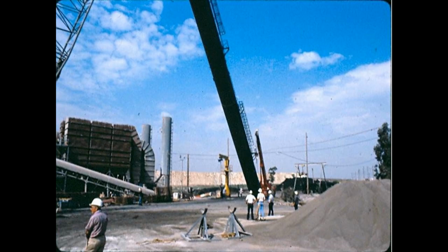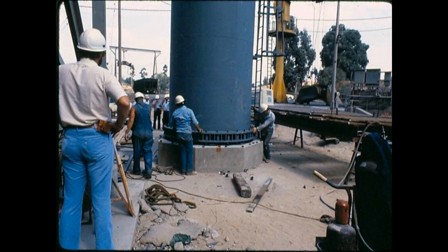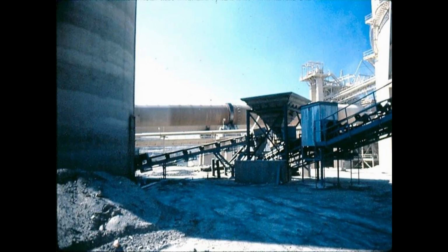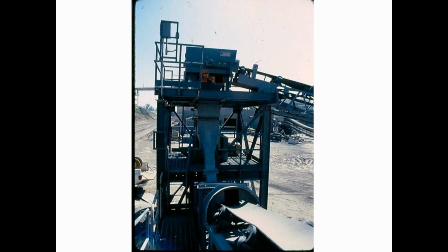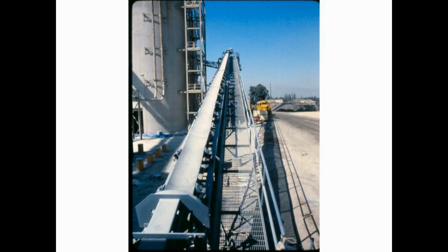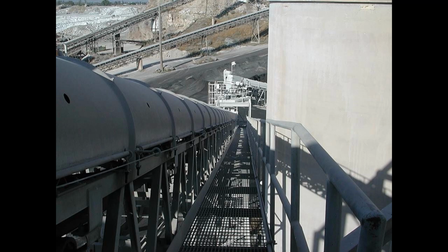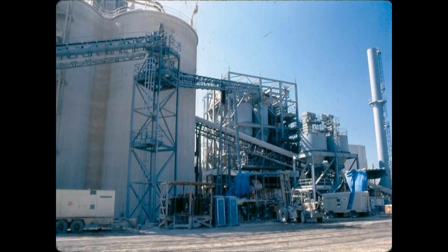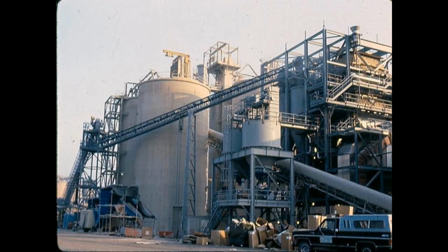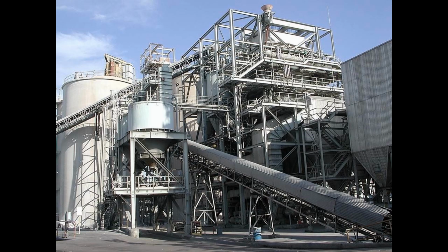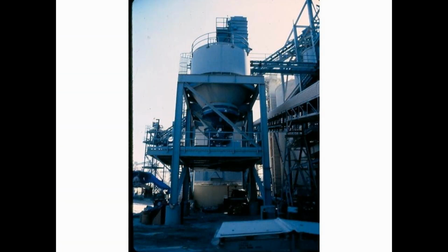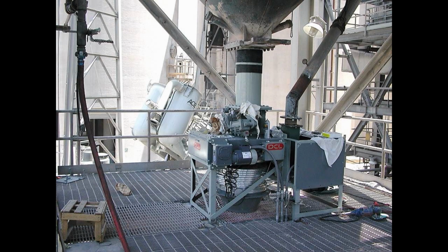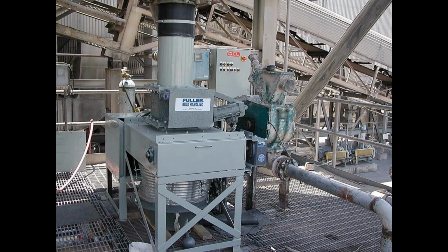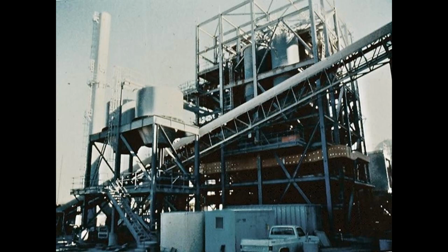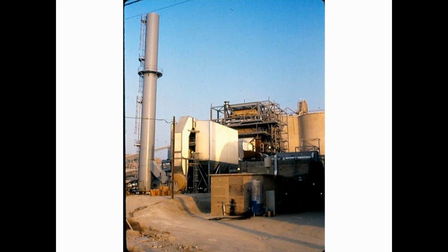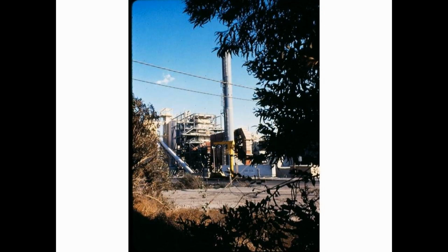The limestone is fed into the combustion chamber where it combines with SO2 to form calcium sulfate, which is then discharged with other solid ash components. The ash material containing reacted and unreacted limestone is discharged from the combustion chamber into an ash storage silo. From storage, the ash is fed into the cement plant raw mix blending process. The use of this ash in the raw mix blending process eliminates the costly problem of ash disposal, which normally represents a major project expenditure.